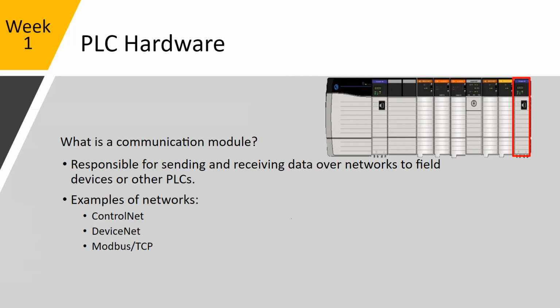The example here of Modbus TCP, that's a universal control protocol. These cards are designed to be able to send and receive information from different field devices. So sometimes these could be called field bus devices. If you're using, somebody had said Siemens, I believe Siemens has their own protocol called Profibus. These are just different versions of Ethernet or ControlNet. They're just sending data for the PLCs to be able to read instrumentation, or we could be doing PLC to PLC communications.